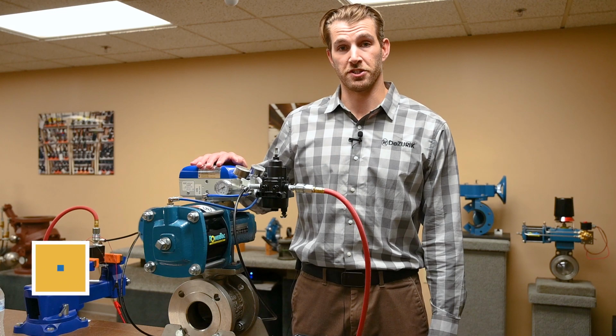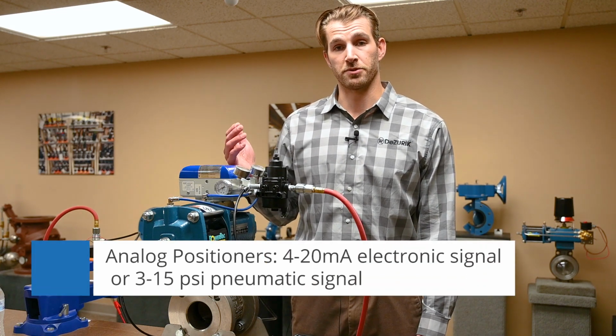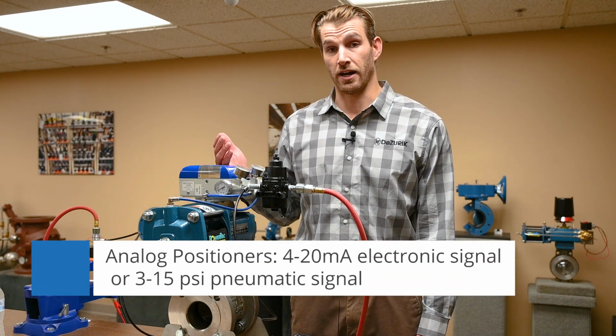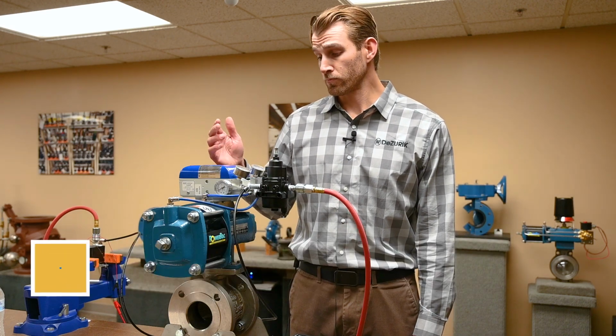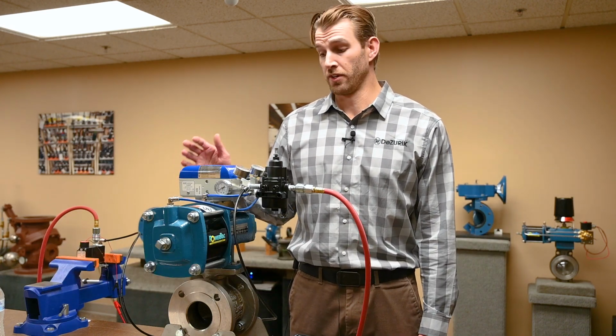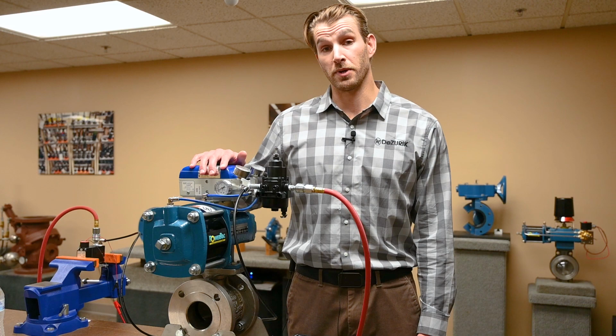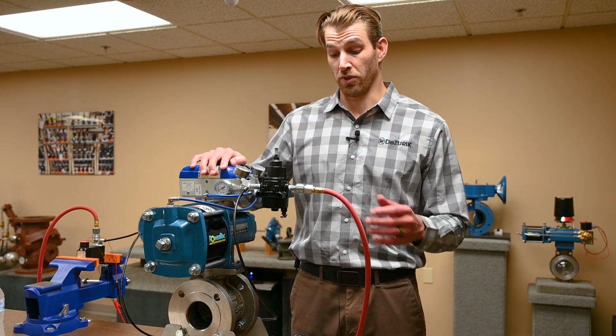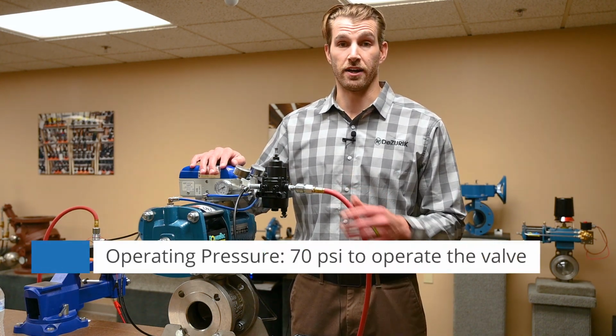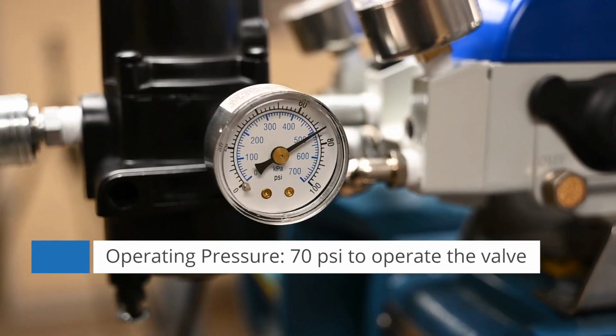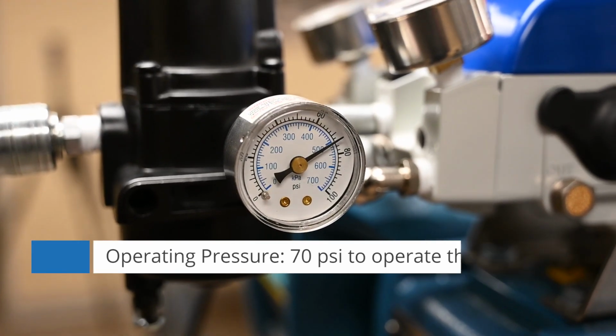Specifically with an analog positioner, it has a 4 to 20 milliamp signal or a 3 to 15 psi pneumatic signal. Oftentimes it is confused between the 3 to 15 psi control signal with the, in this case, 70 psi operating pressure used to actuate the valve.